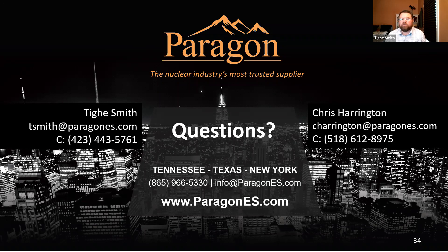What is Paragon's reliability rate on the repairs made on equipment? We did about 419 or so repairs last year and only three or four of those we had returns. The reliability is really high — especially considering that sometimes we're digging out parts of a circuit board to replace it because it's burned up or it's 20 or 30 years old. We won't make compromises when it comes to reliability, and we won't repair something that we don't think we can provide a reliable repair for. How often are we seeing failures during burn-in? It happens, but it's not very frequent. It's typically not the parts we're putting in — it's usually through the burn-in process that some of these cards that have been sitting on the shelf for 20, 30, 40 years and powered up will flush out components that tested marginally when we first received the card.